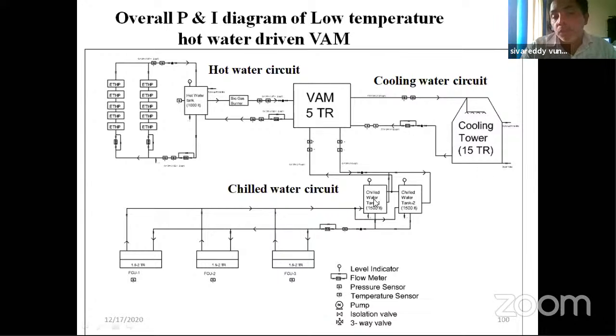Next, the chilled water: we placed 2 chilled water tanks of 1500 liters each. From the chilled water tanks, it is connected to the dryer cabin, not dryer, sorry, the cold chambers. You can see here for hot water we selected only 1000 liters. For cold water we selected 1500, that is 3000 liters.